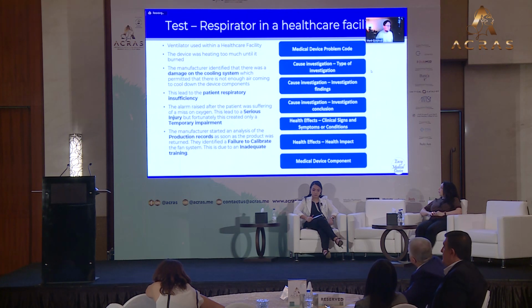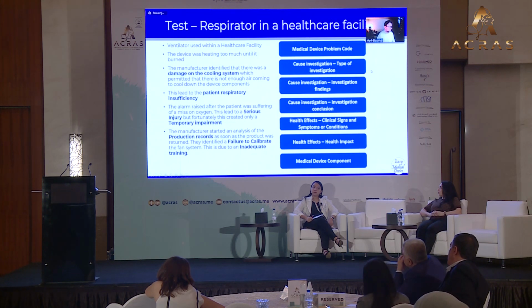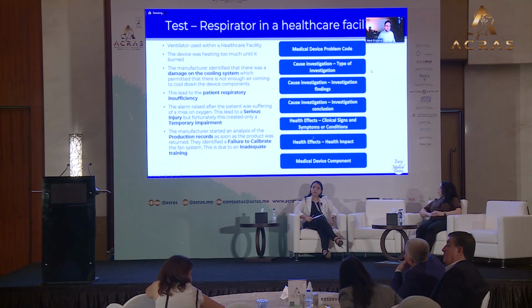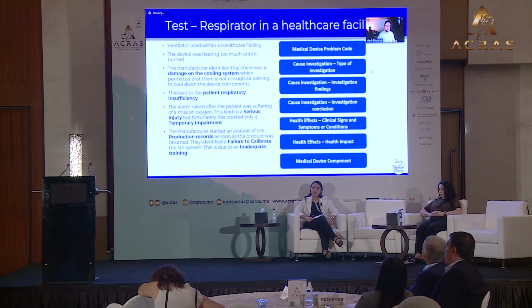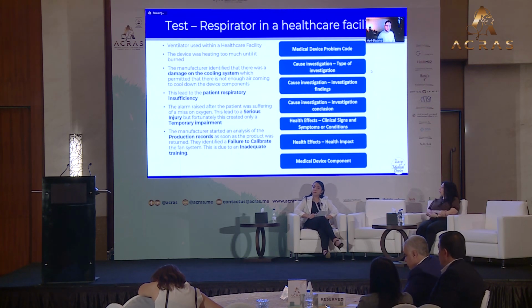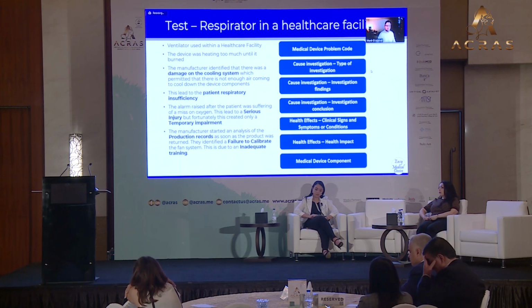So a respiratory issue. The ventilator used within a healthcare facility was heating too much until it burned. The manufacturer identified that there was a damage on the cooling system, which permitted that there is not enough air coming to cool down the device components. This leads to patient respiratory insufficiency. The alarm also raised after the patient was suffering from a lack of oxygen. This led to a serious injury, but fortunately it created only a temporary impairment. The manufacturer started an analysis of the production records. As soon as the product was returned, they identified a failure to calibrate the fan system. This is due to an inadequate training.